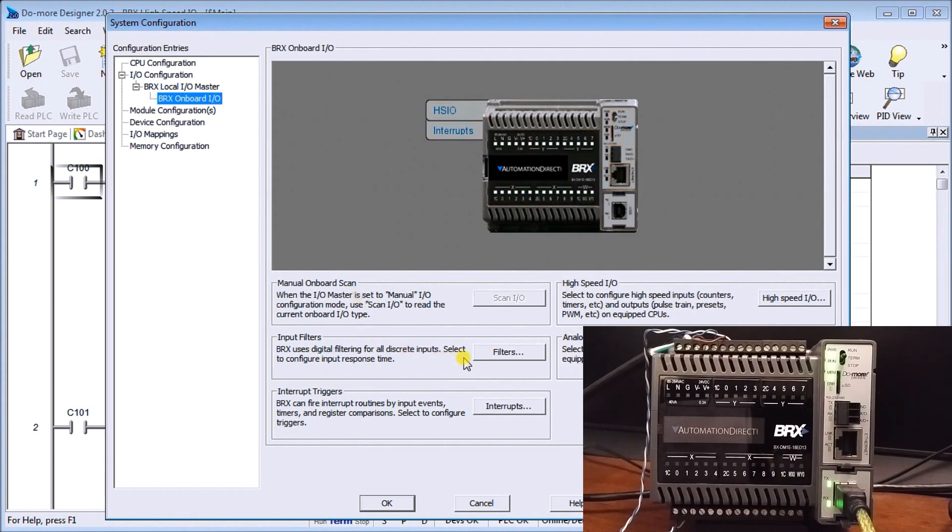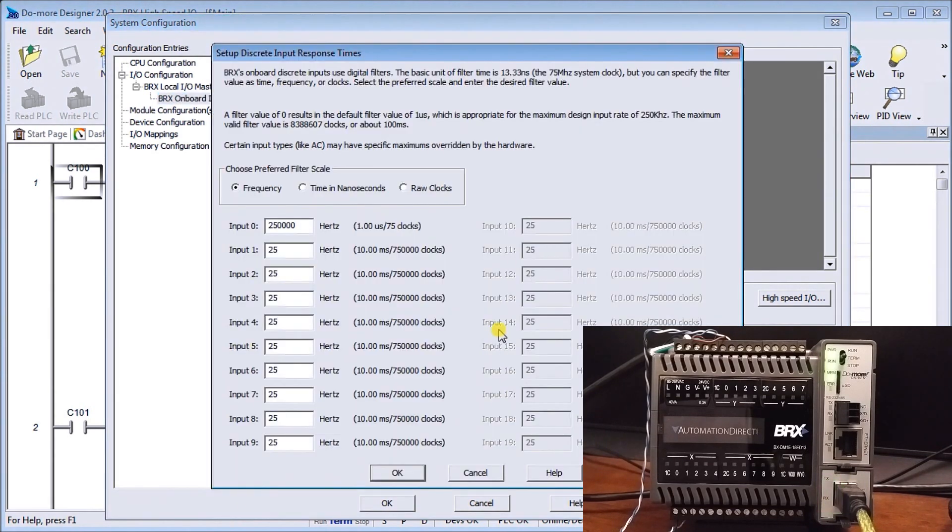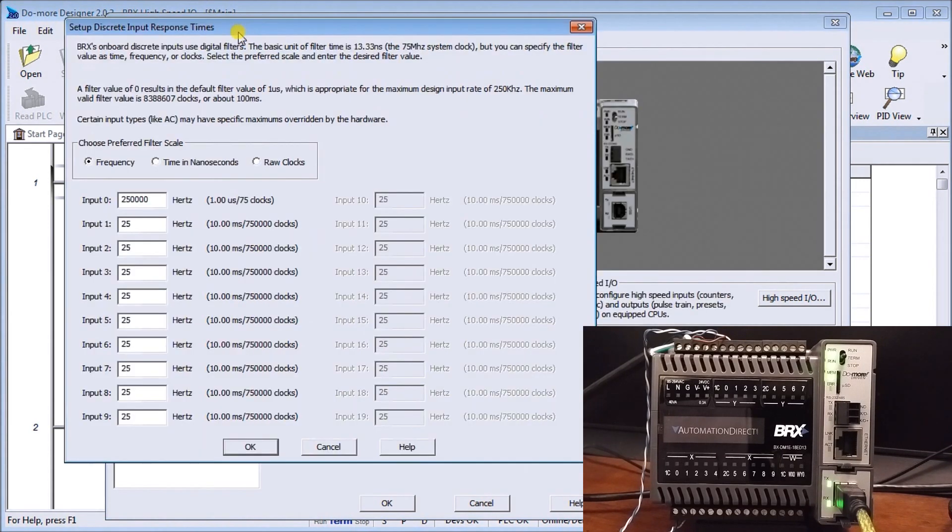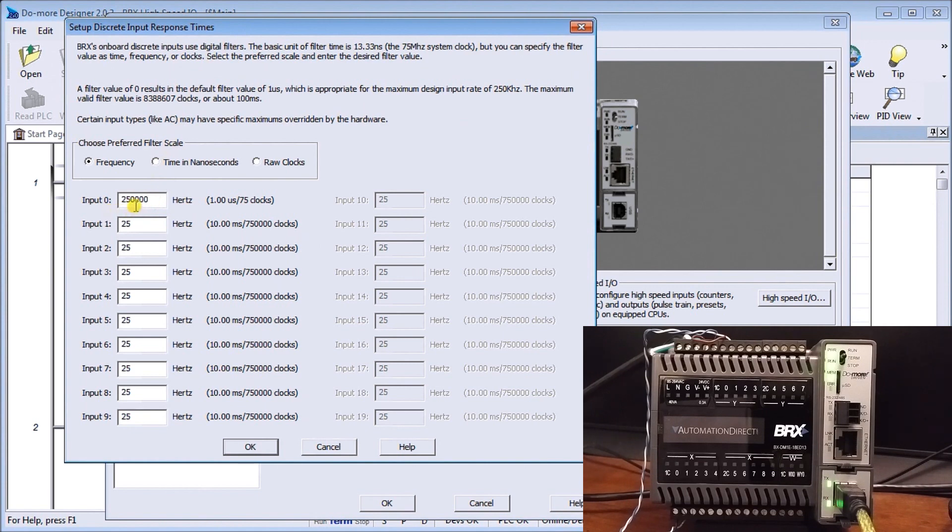And because we're bringing in the signal very fast we need to look at the input filters first of all. And that calls up our input filters and it defaults 25 Hertz. So 25 times a second we can actually bring in that input into the PLC.